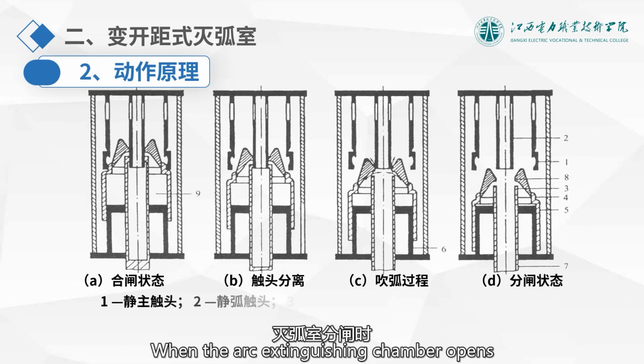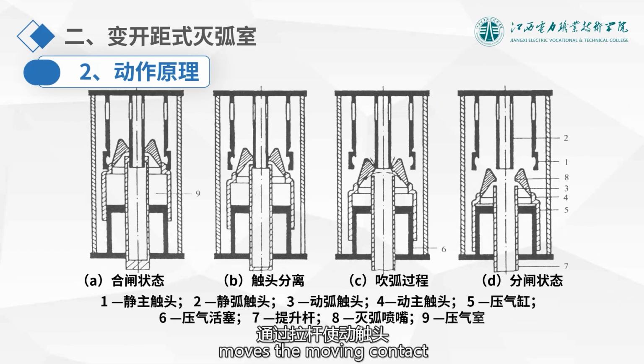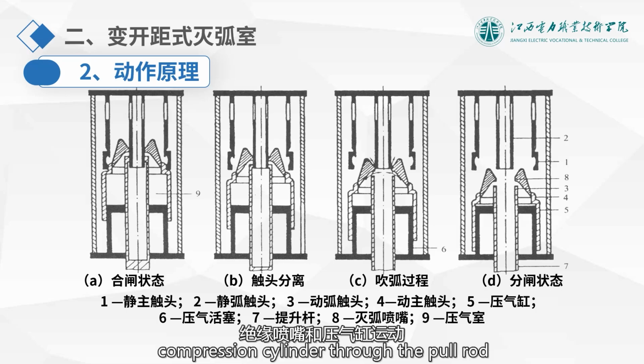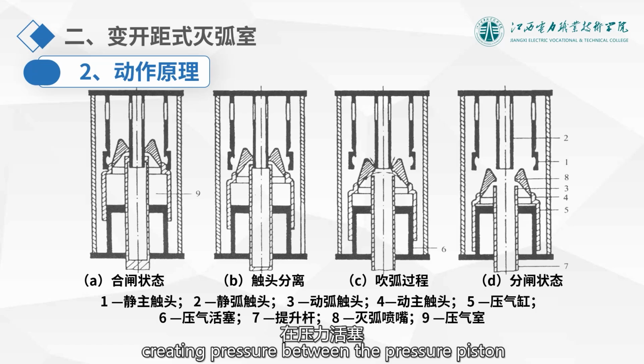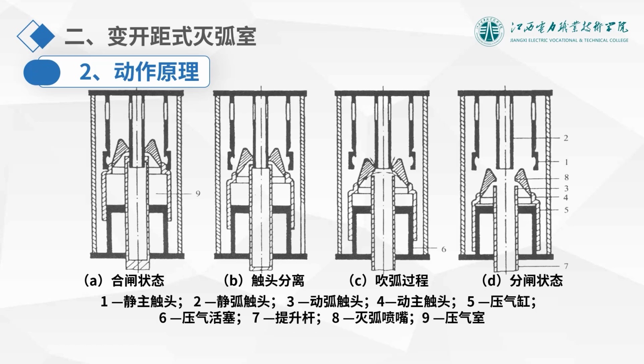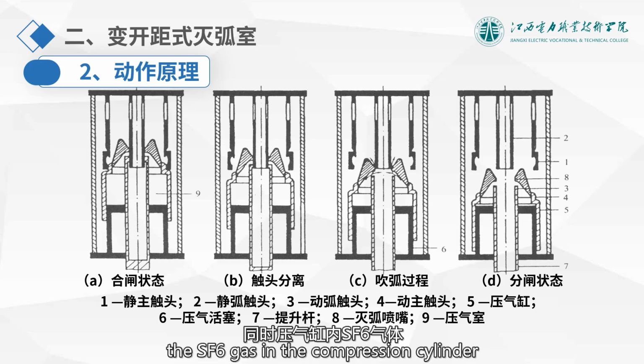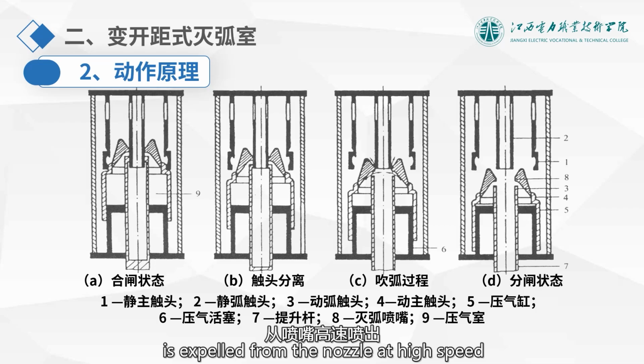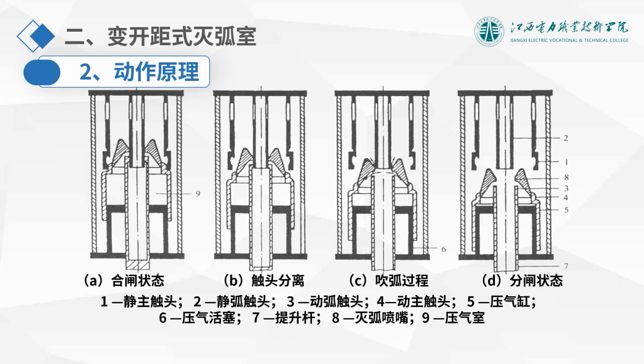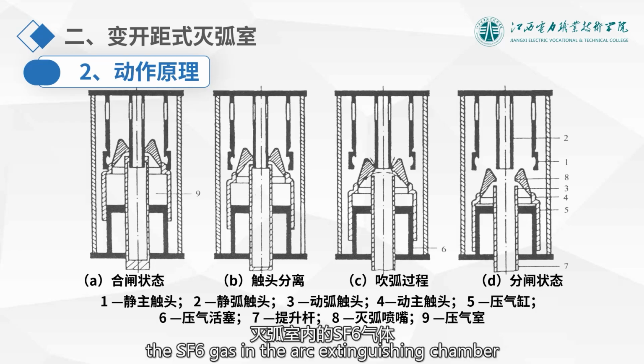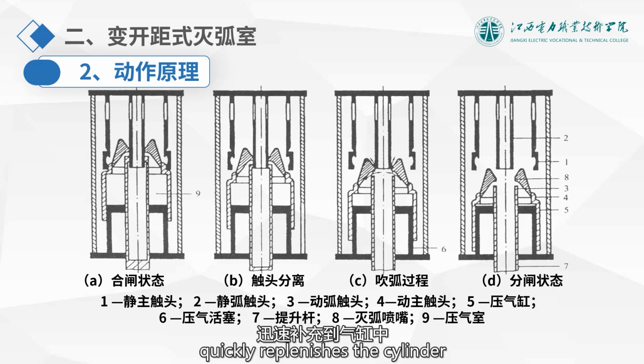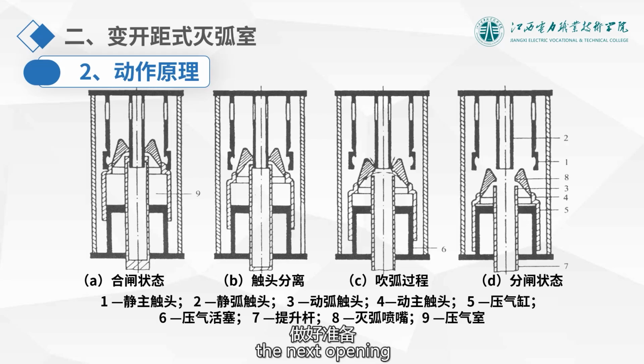When the arc extinguishing chamber opens, the operating mechanism moves the moving contact, arc contact, insulating nozzle, and compression cylinder through the pull rod, creating pressure between the pressure piston and the compression cylinder. When the moving and stationary contacts separate, an arc forms between the contacts. At the same time, the sulfur hexafluoride gas in the compression cylinder under pressure is expelled from the nozzle at high speed, acting on the arc, extinguishing it. During the closing operation, the sulfur hexafluoride gas in the arc extinguishing chamber through the check valve quickly replenishes the cylinder, preparing for the next opening.